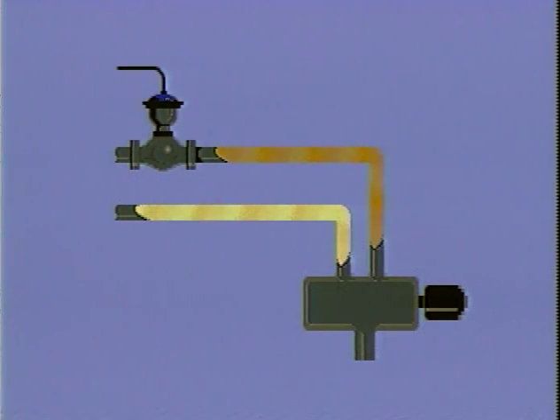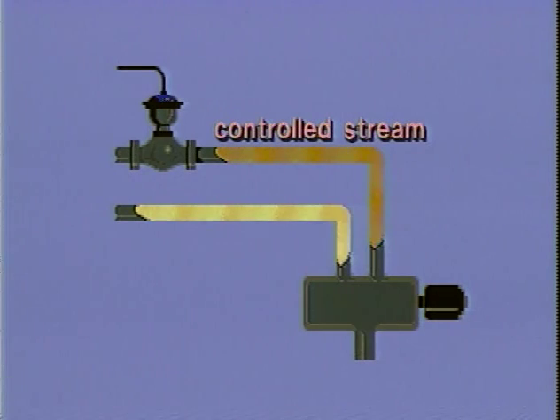Ratio control can be accomplished by controlling both streams, or by using one control stream and one uncontrolled stream. When using an uncontrolled stream, only one of the two flows entering a system is controlled by a ratio controller. It doesn't matter if the other flow varies, so this uncontrolled stream is known as the wild stream. In ratio control, the only thing that matters is that the control stream matches the wild stream in the desired ratio. In this case, the volume of product in one stream must be twice as much as in the other.